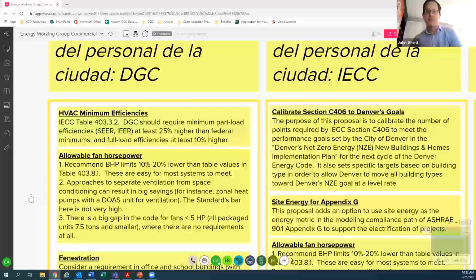So the recommendation here is to see if there's a way, through the Denver Green Code, to incentivize or encourage the specification of systems that have a high part load performance as well. So these I show SEER and IEER. These are just part load composite metrics for the different types of equipment based on capacity. And the suggested recommendation is to require minimum efficiencies at least 25% higher than federal minimums. Now, Denver, currently with our work looking at measures, has also looked at increasing the maximum point total people can get for efficient equipment. So those kind of measures line up from a conceptual standpoint.